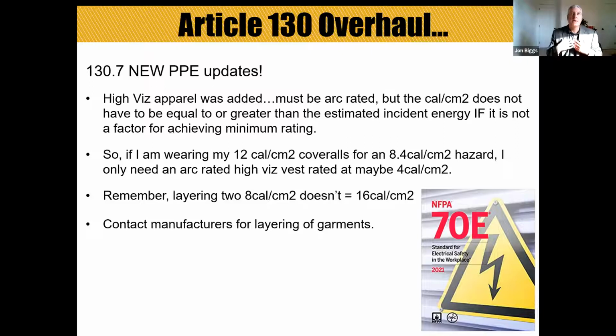So what they mean by that is if I'm wearing already a 12 calorie per centimeter squared pair of coveralls for my arc rated protection from this 8.4 calorie per centimeter squared hazard that I'm working on. If I've got those coveralls on, that is the primary factor in me achieving minimum rating. So I've got garments on that exceed my hazard that I'm working on. So that's my arc rated protection. Now, if I have to wear a high visibility vest, I don't have to wear a vest rated for the hazard. I can wear a vest that's just rated at 3 calories or at 4 calories per centimeter squared, as long as it's something that is not going to melt. Okay, so that's the focus here.